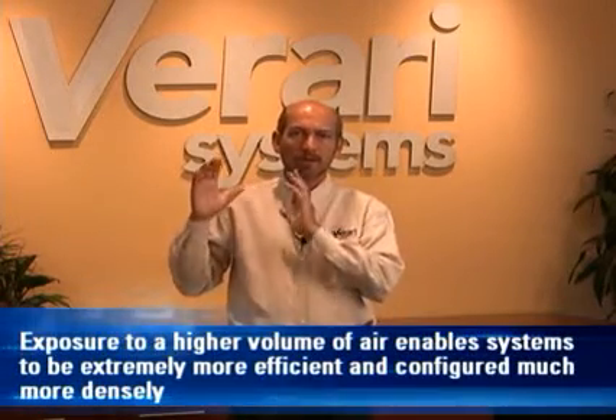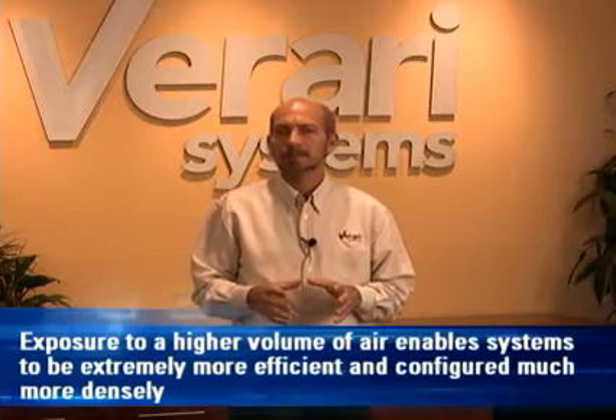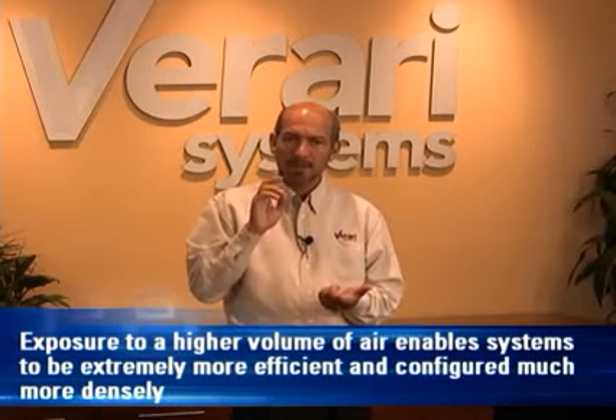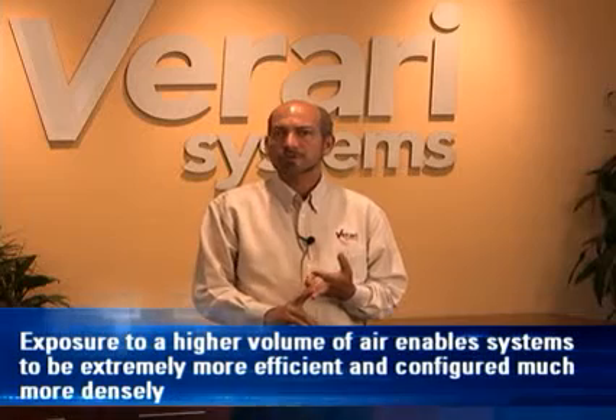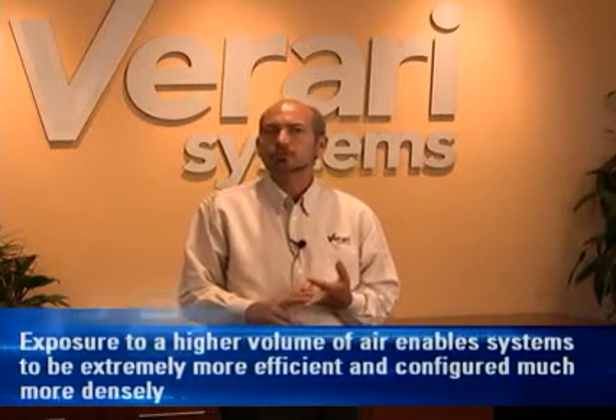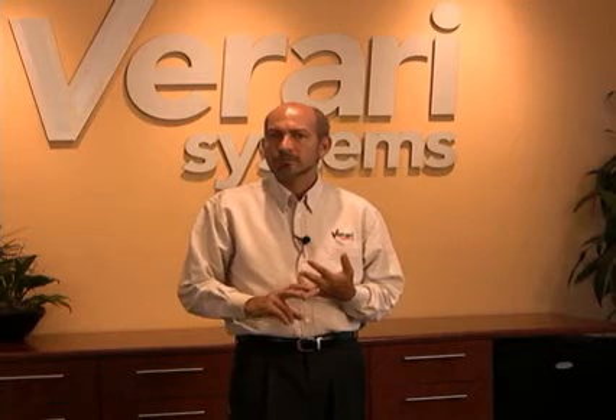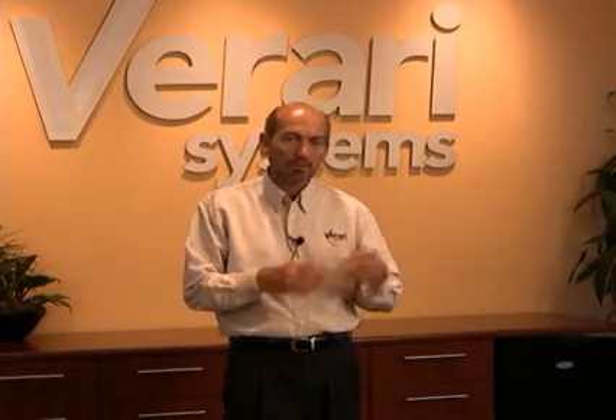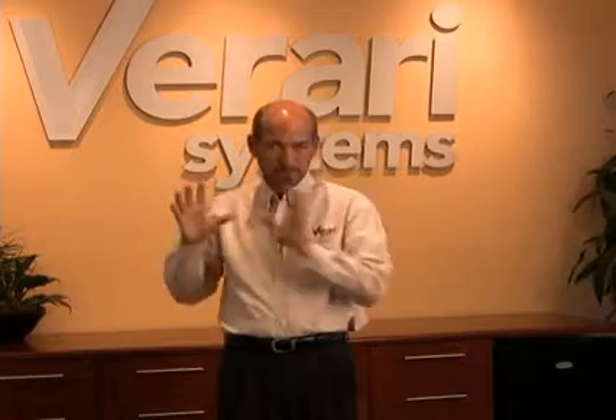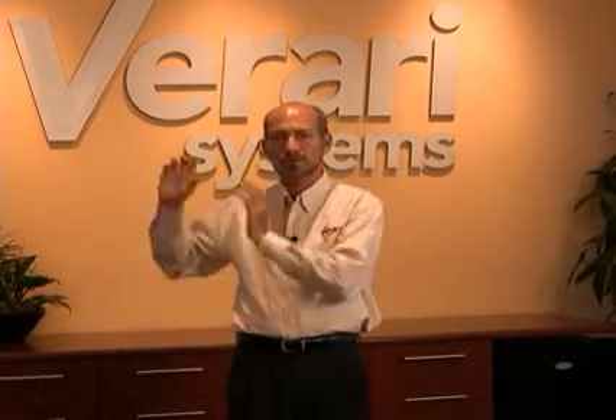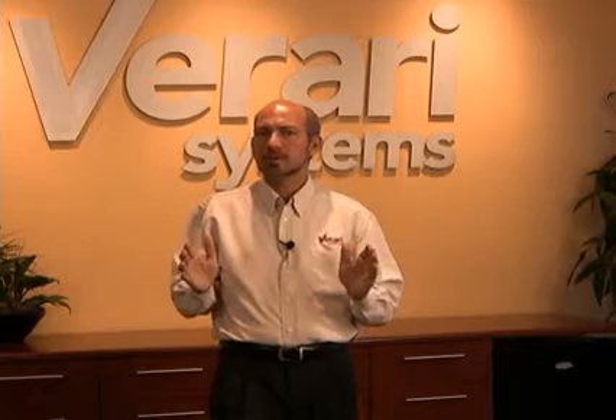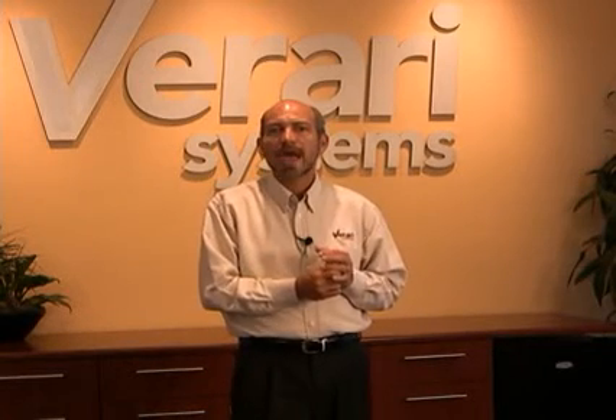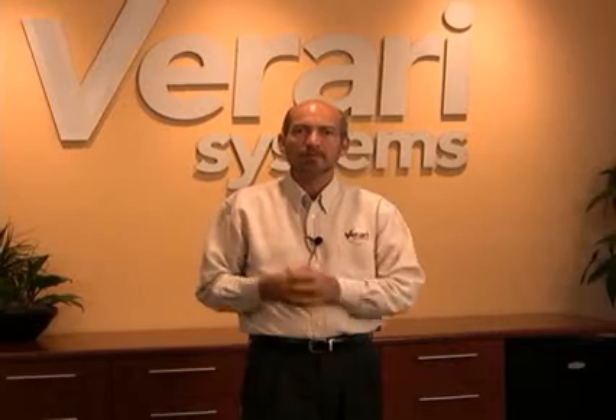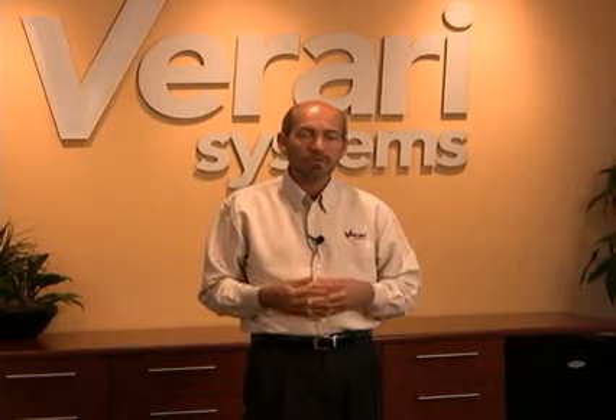And anytime you're talking about more volume, you're talking about a higher degree of reliability. So we wound up with a system that was denser, far more efficient from how much fan power is being used to cool the system, a system that wound up being far more reliable. We're seeing the failure rates on our rack mount versus, and these are our systems, our rack mount versus our blade architecture, the same components, and a failure rate that's nearly half that of the rack mount. The blades are that much more effective at using the power to cool and the power to keep the systems in a nice shape and nice conditions.